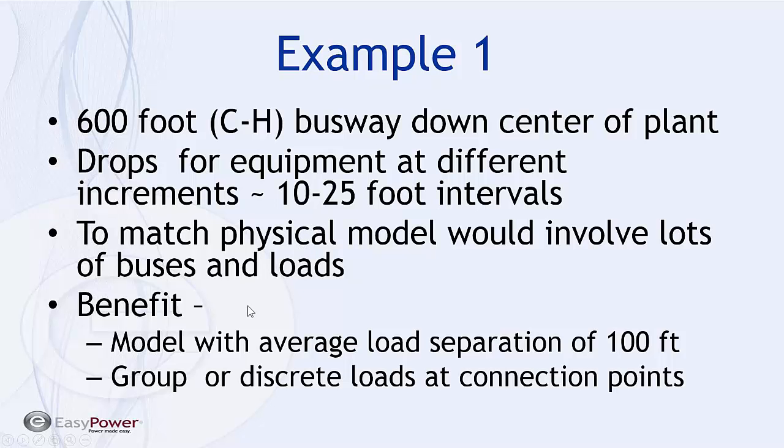The advantage of tackling it with this paradigm difference is that if we model the average load separation, or we set a standard separation between load connection points of 100 feet, and then we group our loads at those connection points, it gives us a way to make updates or change the model pretty much as simply as we do the physical installation.